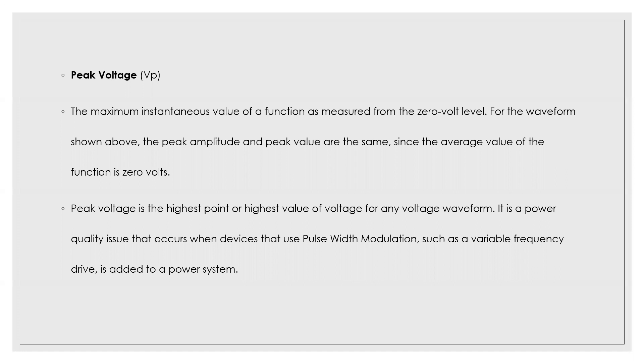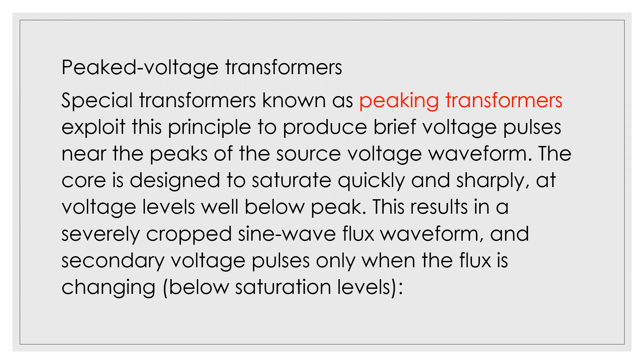Peak voltage transformers. These are special transformers known as peaking transformers. They exploit this principle to produce brief voltage pulses near the peaks of the source voltage waveform. The core is designed to saturate quickly and sharply at voltage levels well below peak. This results in a severely cropped sine wave flux waveform and secondary voltage pulses only when the flux is changing below saturation levels.